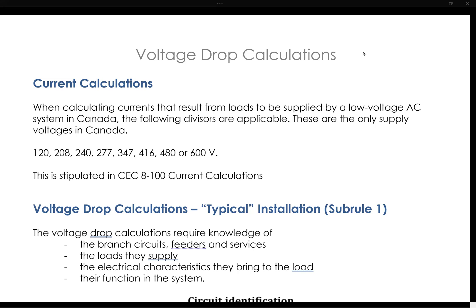So the Canadian Electrical Code Section 8, Rule 102 provides a guideline for calculating the voltage drop appropriately. And before that, Rule 100 in Section 8 just reminds us that when we're calculating the currents that result from these loads, we have to remember our supply voltages that are available in Canada, which are listed here. These are all available, some more common than others, but these will be our divisors when we are doing our voltage drop calculations.